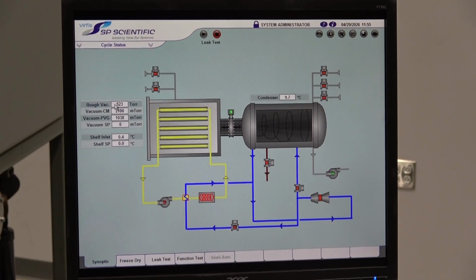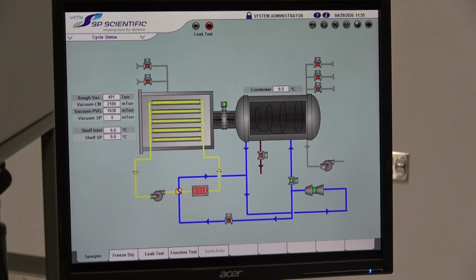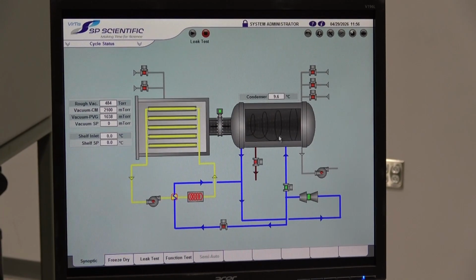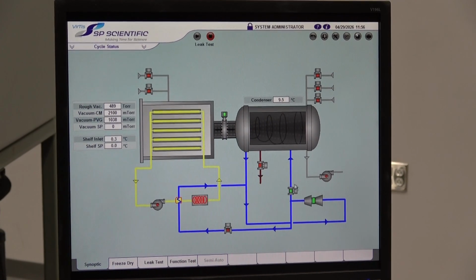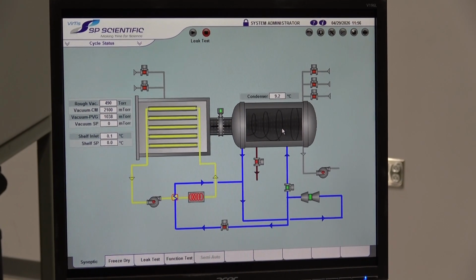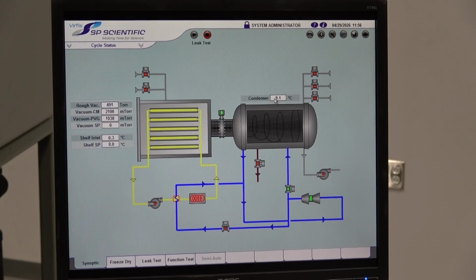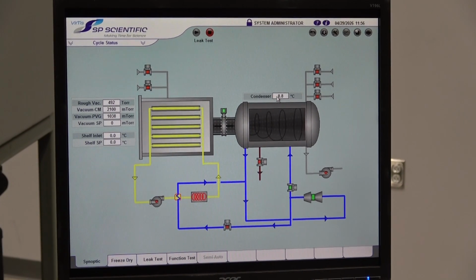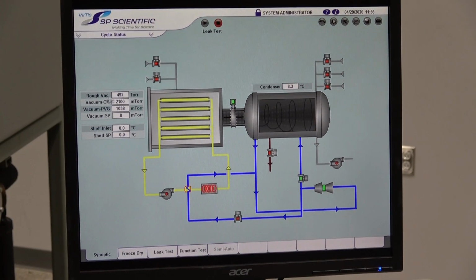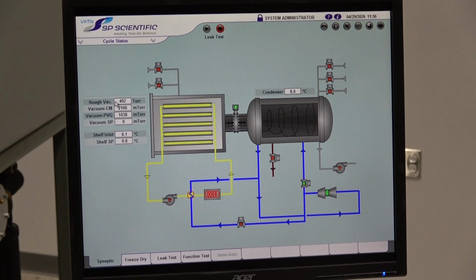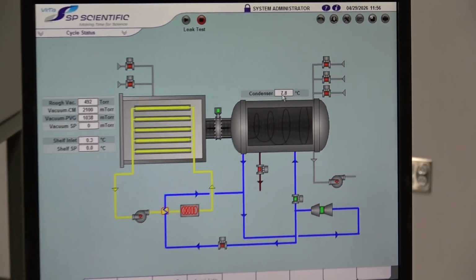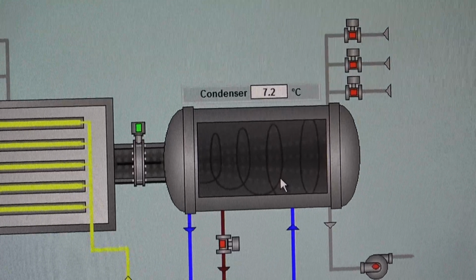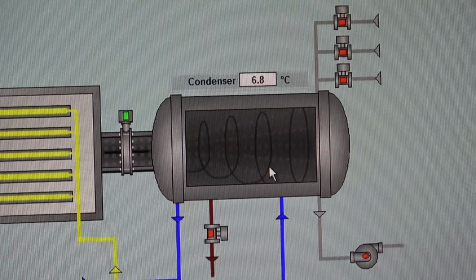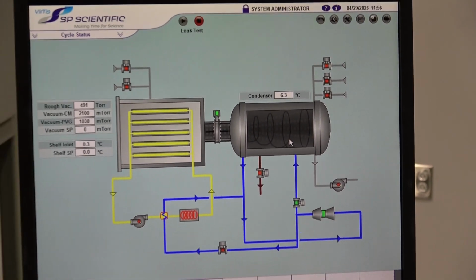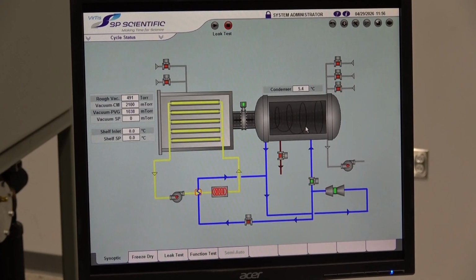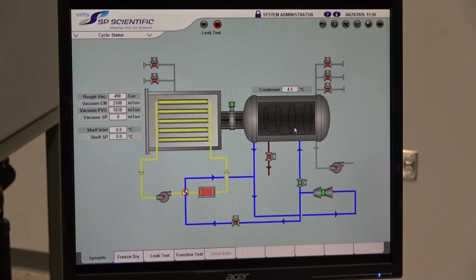It's going to pull down to 500 torr. As you can see, as soon as it hits 500 torr, the vacuum pump will shut off, and now the compressors are running and it's pumping refrigeration into our condenser here through this valve. So now what's going to happen is our condenser temperatures are going to just start dropping down, and it should get down to about -40, -45, and then our vacuum pump again shall kick on and pull us down to our deeper vacuums. So you can see how instantaneous this thing just moves that needle really quick, and it's just a massive piece of equipment, and for that refrigeration system to kick on and just really start moving the needle, like I said, just a real industrial production machine that has very little use on it.